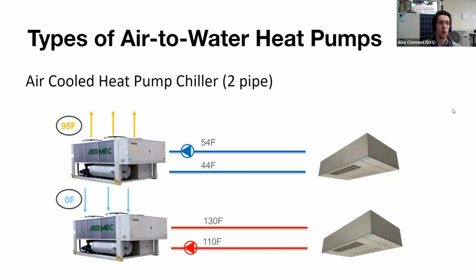So next we'll get into another type of air source heat pump. This is an air source heat pump machine that heats or cools water. It's an air-cooled heat pump chiller, also called a reversible chiller. These machines are two-pipe machines, so they either have to be all in heating or all in cooling. In the summer on a 95-degree day, you're going to be able to supply 44-degree water to your space. Here on the right, those are just some fan coils, for example, that would use that water to heat or cool the space, but they can also be different kinds of units. In the wintertime, you'd be supplying 130-degree water and usually getting 110-degree water back from your fan coils.